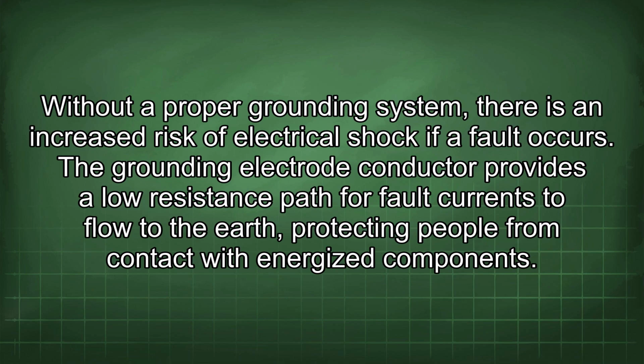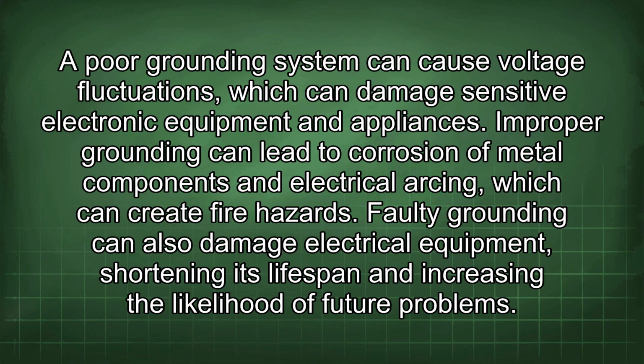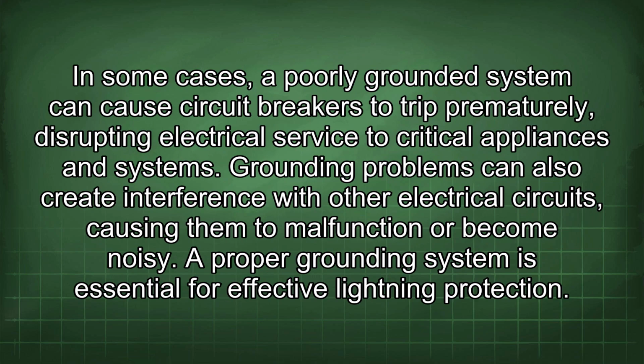Without a proper grounding system, there is an increased risk of electrical shock if a fault occurs. The grounding electrode conductor provides a low resistance path for fault currents to flow to the earth, protecting people from contact with energized components. A poor grounding system can cause voltage fluctuations, which can damage sensitive electronic equipment and appliances. Improper grounding can lead to corrosion of metal components and electrical arcing, which can create fire hazards. Faulty grounding can also damage electrical equipment, shortening its lifespan and increasing the likelihood of future problems. In some cases, a poorly grounded system can cause circuit breakers to trip prematurely, disrupting electrical service to critical appliances and systems. Grounding problems can also create interference with other electrical circuits, causing them to malfunction or become noisy.